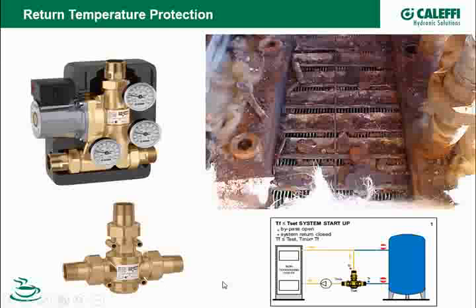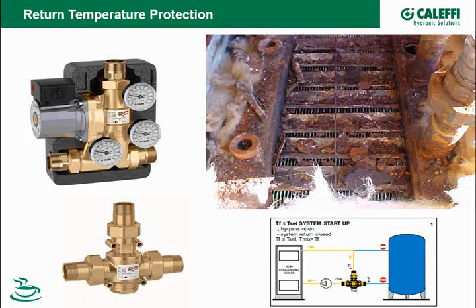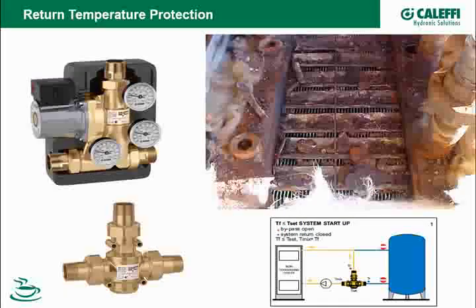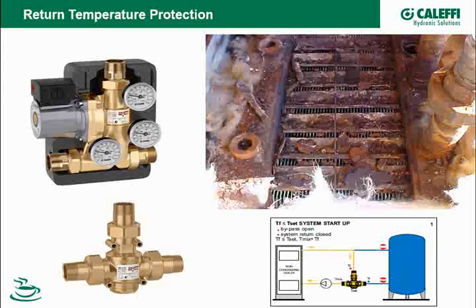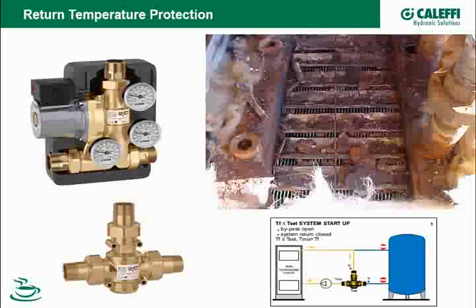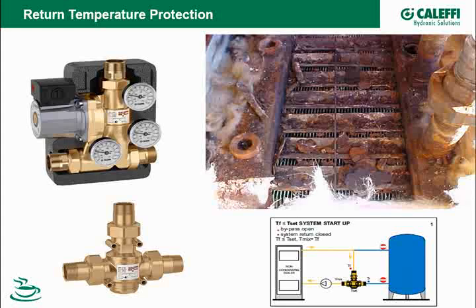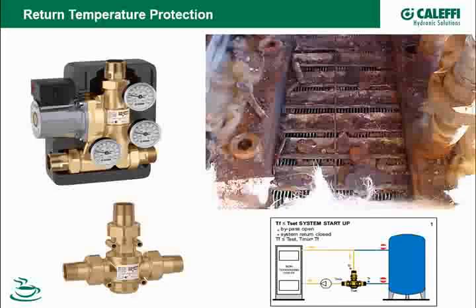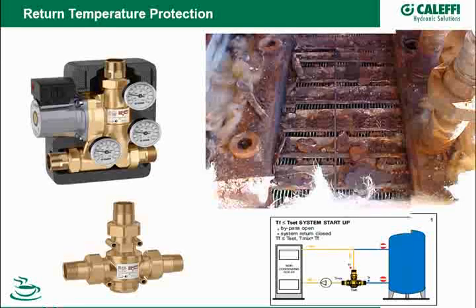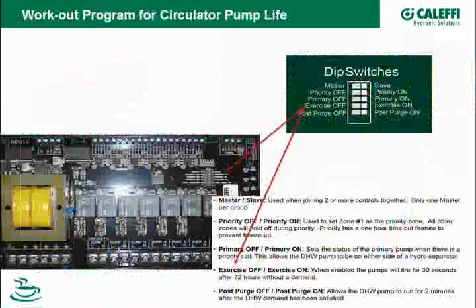The other place that this is critical is that a lot of guys are starting to look at wood or biomass boilers as a backup, or as a first source of heat if they're on oil heat, or propane prices are going through the roof. We're seeing more and more pellet and wood boilers being installed as a secondary source or a primary source. That boiler needs to be protected with return water protection because they can creosote up pretty badly, and you can have some issues with that. So let us know if we can help with that. We've got plenty of piping schematics and different ideas for installing those.